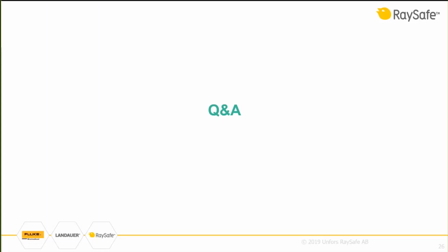And when you look at the high energy rooms of therapy vaults, even if you have the machine set on many mega electron volts, the mean energy is often much lower, so a couple of hundred keV, or maybe up to a mega electron volt, but often lower than that. Okay, great.